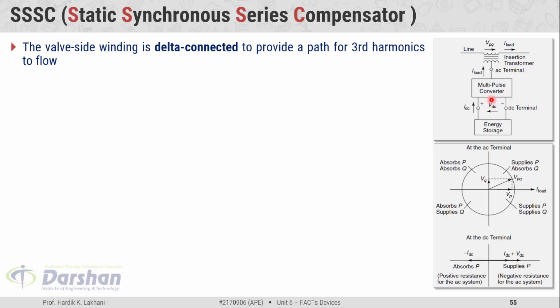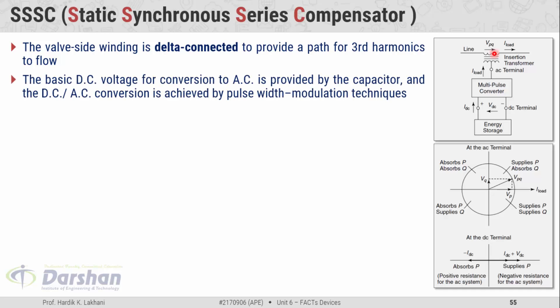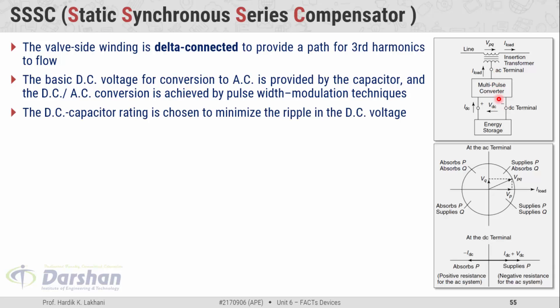The valve side winding is delta connected to provide a path for third harmonic to flow, so that the third harmonic does not go into the system. The basic DC voltage for conversion to AC is provided by the capacitor, meaning the energy storage element could be a capacitor. The DC to AC conversion is achieved by the pulse width modulation (PWM) technique. By choosing an appropriate PWM technique this DC to AC conversion can be done. The DC capacitor rating is chosen to minimize the ripple in the DC voltage.